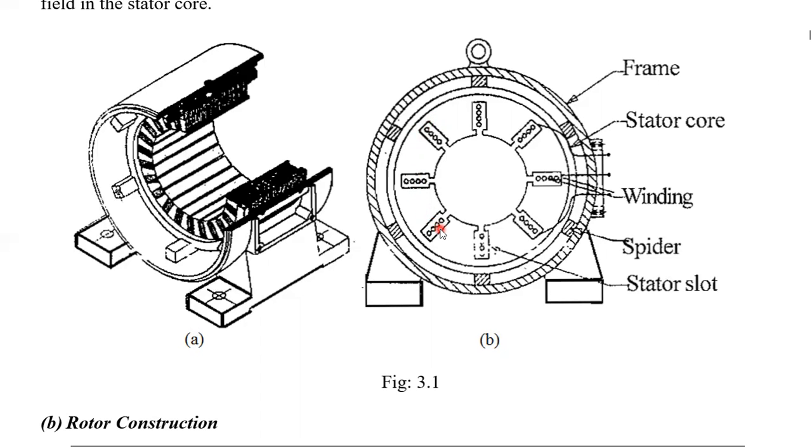So what happens? If there is a relative speed between the rotor and stator, EMF is induced in the rotor, and immediately current is developed in the copper bars of this squirrel cage induction motor. Then force is developed according to the Lorentz force, and the motor again rotates, now in the anti-clockwise direction. Am I right? In this way, the direction of rotation of the motor is changed by changing the phase sequence. Understood?